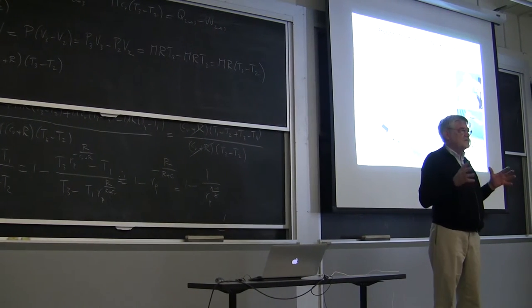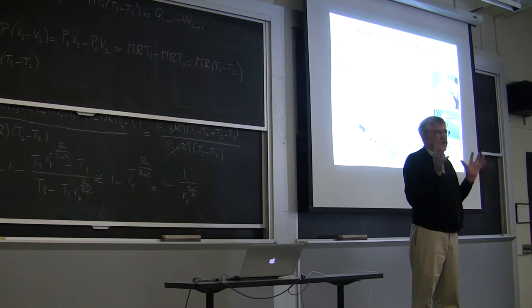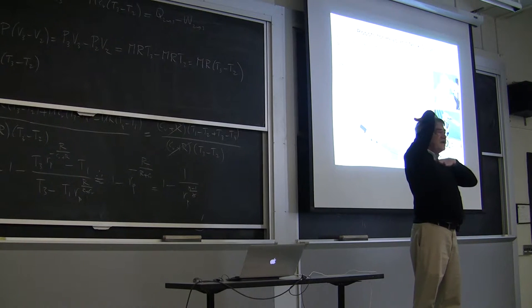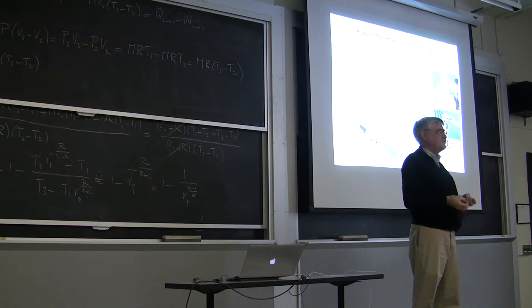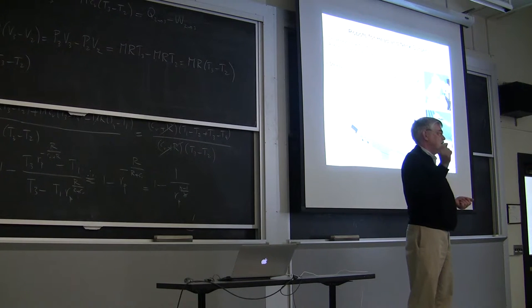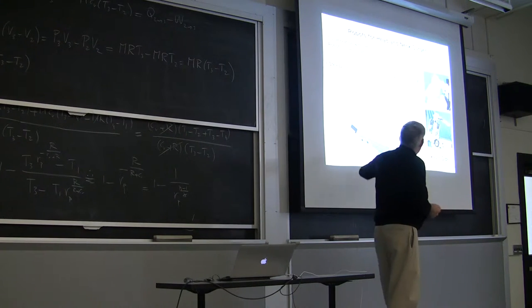Here, what we wanted to do is see, could we design a robot whose work volume and characteristics were well tuned to head and neck surgery? There's a lot of surgery from here to here, so you need a work volume about like that with fairly high mobility and high precision. This robot has about 25 micron precision. Not quite as stiff as I want, but I can show you.